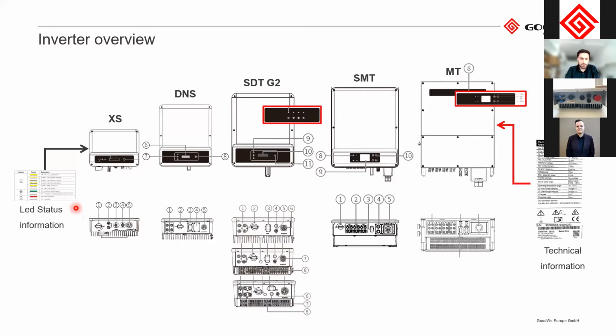Something that's also good to know is that on the side of each inverter, on the left-hand side, you will have a sticker that explains what different LED lights do or indicate. So either if it's on, if it's feeding to the grid, if there's an error, if there's some communication error with the Wi-Fi module and such, you can see that here. And this information is also found in the manual.